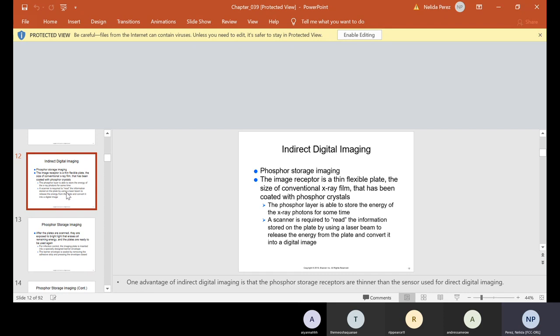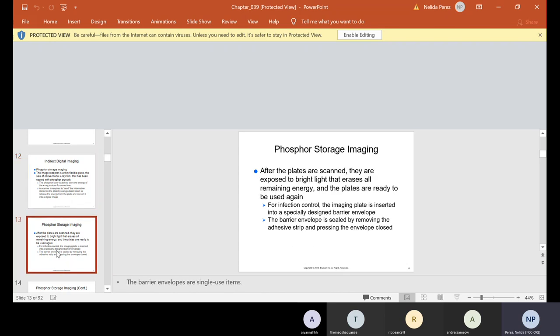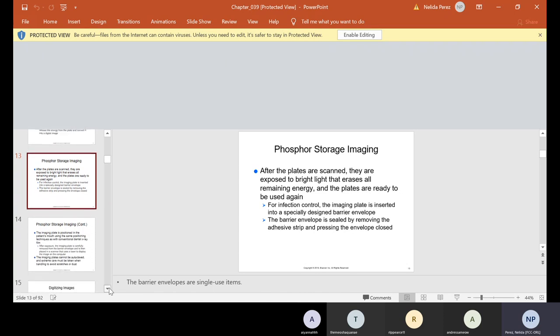Indirect imaging uses phosphor storage imaging. The image receptor is a thin, flexible plate the size of conventional x-ray film, coated with phosphor crystals. The phosphor layer stores the energy of x-ray photons for some time. A scanner using a laser beam is required to read the information stored on the plate and convert it into a digital image. Please take a look in your Kindle book — the phosphor plates and digital imaging sensor look a little different. The phosphor plates require a scanner; sensors go directly into the computer or wirelessly.